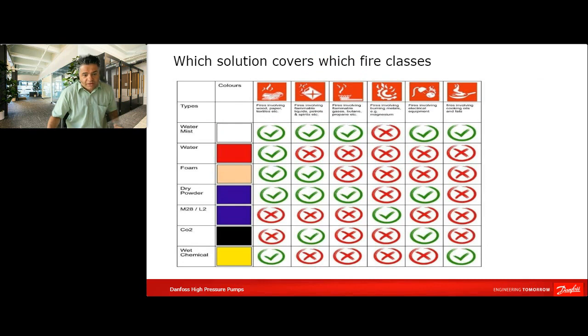I just want to show you an overview of the existing extinguishing agents in general, not dependent on data centers specifically. You can see in the first column, on the left hand, the possible extinguishing agents in the world. It can be water-based, like water mist or sprinkler. It can be a foam system, a dry powder, or other chemical gases. And you can see on the first row at the top that we have different fire types, fire classes that exist and could exist in a data center building as well. If you look at the matrix, you can see that the only extinguishing agent which could cover most of those fires is water mist.